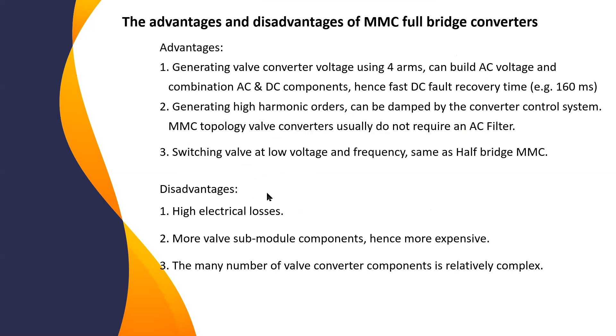And here, the same for half bridge, because we generate discrete voltage. At the end, the harmonics are very, very low. The disadvantage here, because we have more equipment, we have more losses. And because we have more equipment, the valve or converter will be more expensive. And at the end, because we need more components here, of course, the circuit will be more complex compared to half bridge.